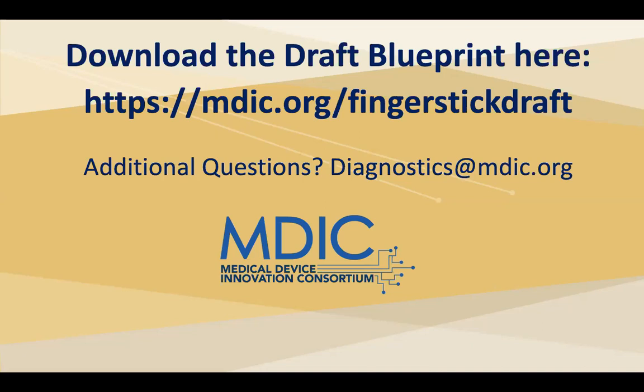Next comment. Can you comment on the recommended sample size in the method comparison study for a qualitative assay? For example, how many positives would be required? I don't recall. Alva, do you remember if we indicated? Yeah. We have not considered qualitative tests in the description of the document as much. It is mostly given for a quantitative measurement, because that's where the analytical errors were considered as a problem. So this is primarily to address a quantitative assay. For a qualitative method, you may have other guidances you may want to refer to. So this is specifically for a quantitative assay where the sampling techniques or the number of data points are not sufficient to demonstrate the validity of a test, which is what is addressed in this document.